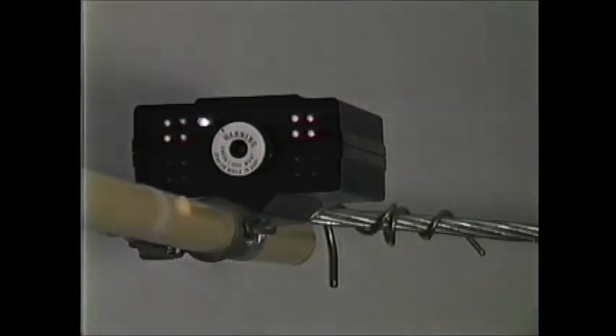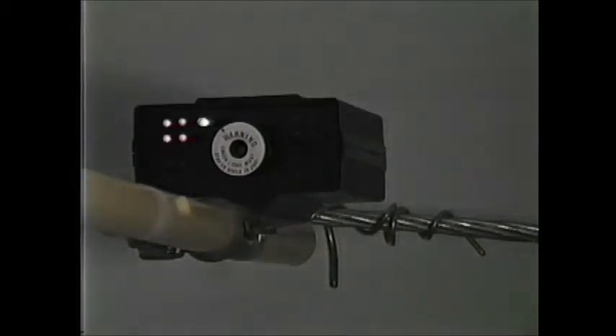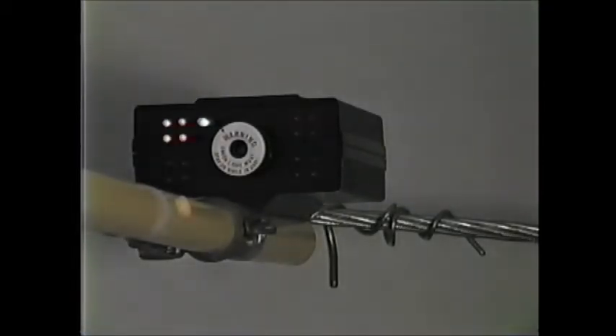This would be the indication you would get for a 4,800 volt system or a 7,200 volt system if you had full system voltage. If you were testing a 12 KV, 25 KV, or 35 KV system, you would know you have more than 2,000 volts but certainly less than system voltage.